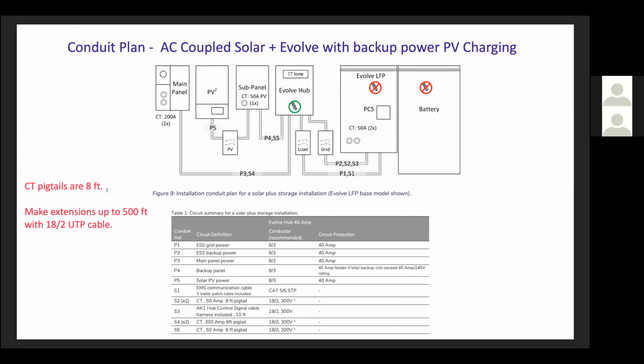The CT pigtails, so the CT wire pairs that come with the CTs, are a standard 8 feet long. And they will reach from the hub to the battery and to a sub panel, for example, if they are located adjacent to each other. But getting all of that to work, and then also having those 8-foot pigtails reach to the main service panel, is sometimes a challenge. So they can be extended, but you've got to make sure that you use manufacturer spec wiring and splicing method when you do that. Those extensions can be up to 500 feet when done correctly, and those specs are given as well in the manual.